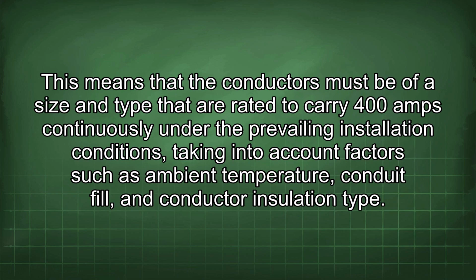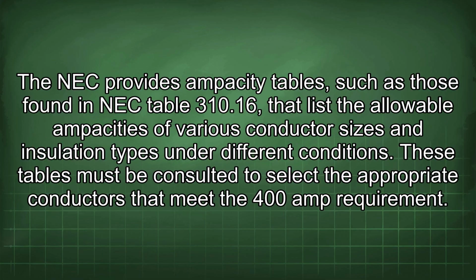This means that the conductors must be of a size and type that are rated to carry 400 amps continuously under the prevailing installation conditions, taking into account factors such as ambient temperature, conduit fill, and conductor insulation type. The NEC provides ampacity tables, such as those found in NEC Table 310.16, that list the allowable ampacities of various conductor sizes and insulation types under different conditions. These tables must be consulted to select the appropriate conductors that meet the 400 amp requirement.